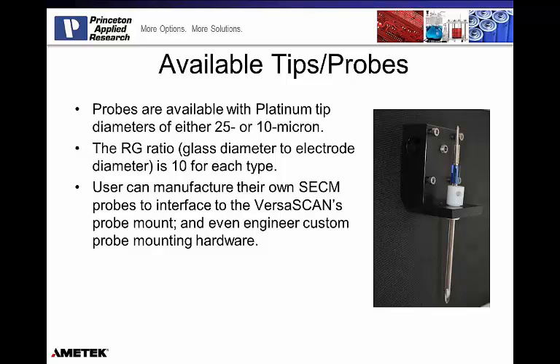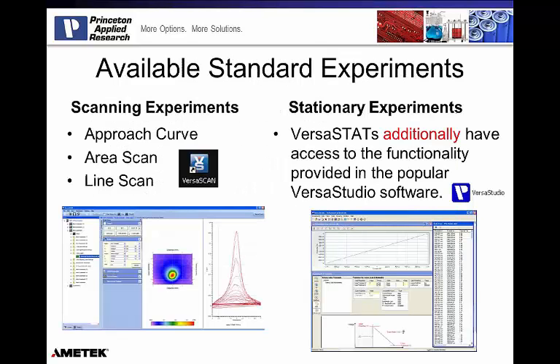So often SECM probes are commercially available, but again, they are just ultra-microelectrodes. There are many well-characterized ways to create your own ultra-microelectrode with glass-drawn pipettes. So in an SECM system, we have potentiostats and positioning systems and probes, and we are going to be doing experiments that coordinate the movement of probe position with the measurement of the potentiostat. It's that coordination and integration of the positioning system and the electrochemical control and measure that's one of the real values of an SECM system.